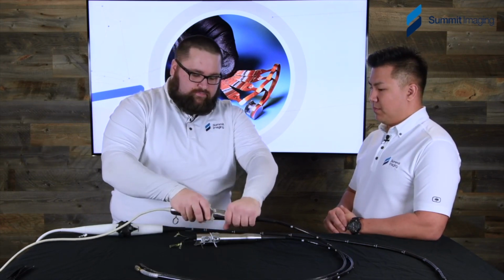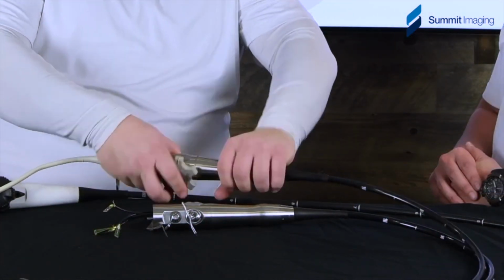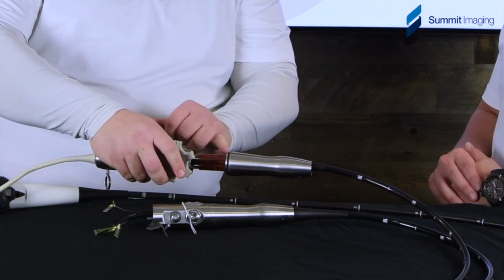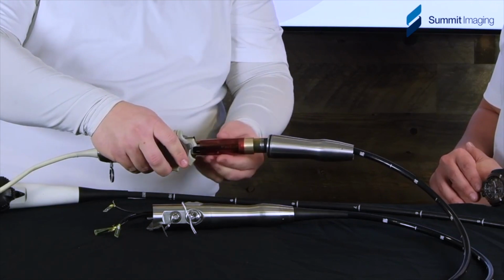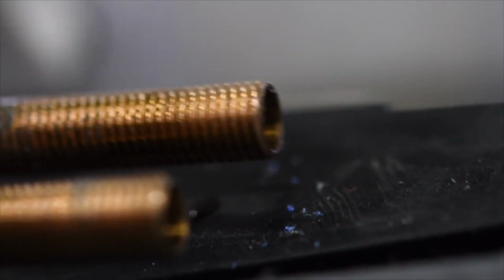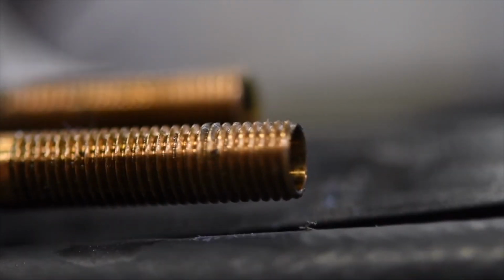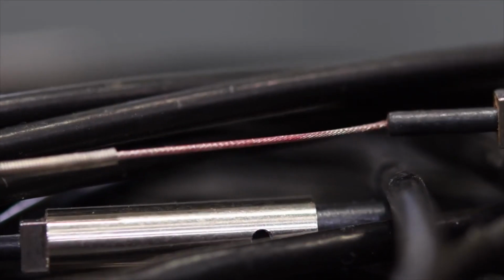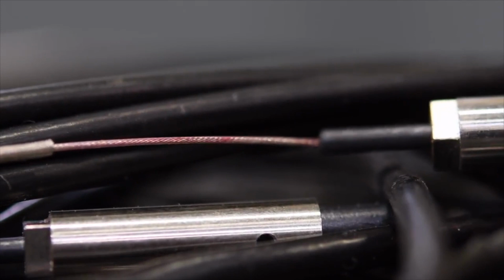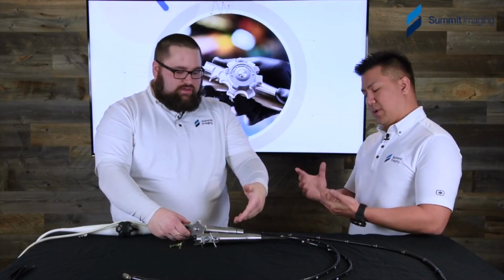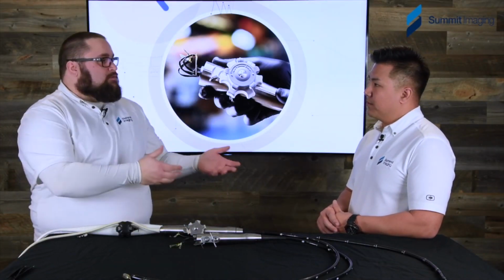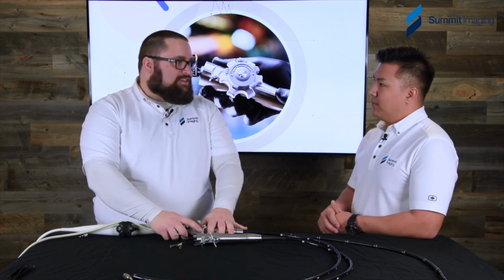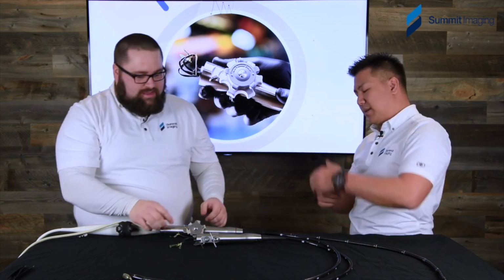And they're getting their wet glove all on here, and there's an O-ring right here, but a few drops will get in and just sit. And this takes a lot longer. This means it's gone through a few processes where it's gotten wet, but maybe your steering mechanism starts to rust. Your lines start to get eaten at. And the probe fails. And you think it's the tip, but it's actually up here. Or we talked about hanging it to store it. That water gets in there. And then it hangs and goes down.